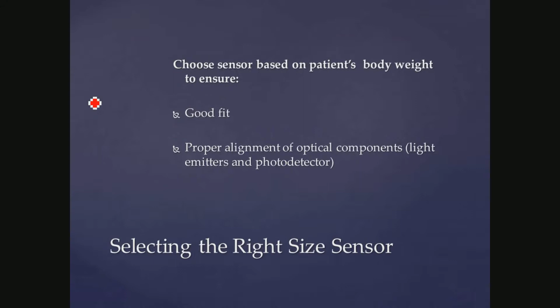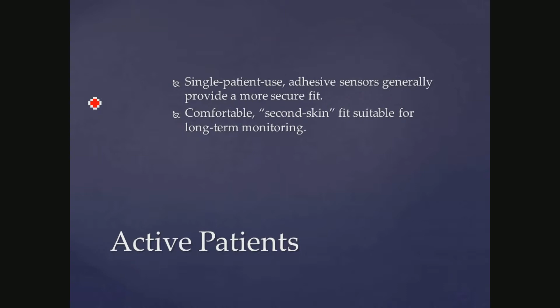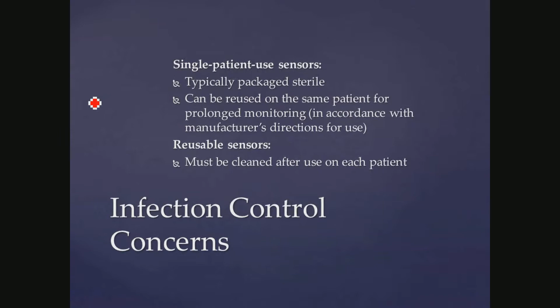That means that the alignment of the photodetector and light emitters, light emitting diodes, have to be balanced across from each other. Active patients are probably going to be done better with a single patient use sensor because the multi-use sensors have more of a tendency to fall off, if nothing else. That second skin fit refers to like the Band-Aid that you end up having. You can get a far better sensor placement for long-term monitoring. They are typically packaged sterile. They can be reused. Where a reusable sensor, you have to clean.